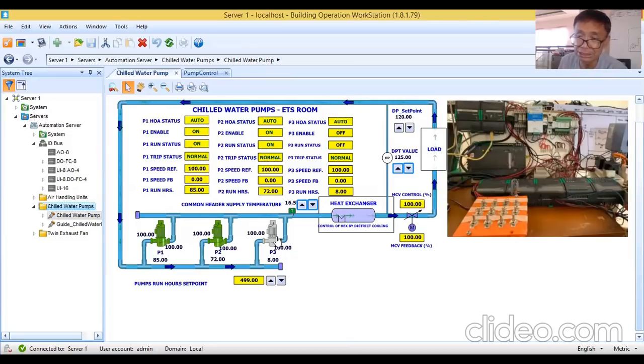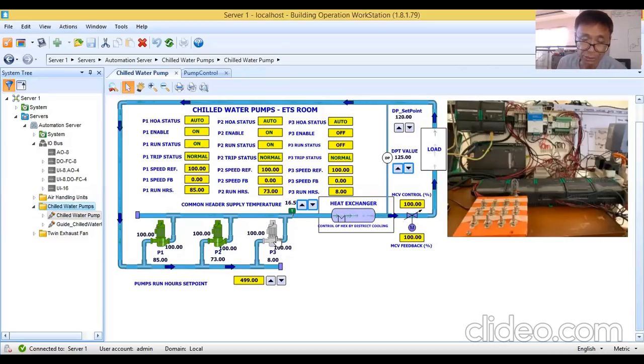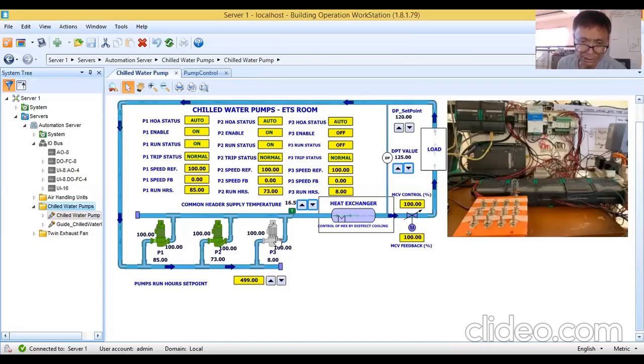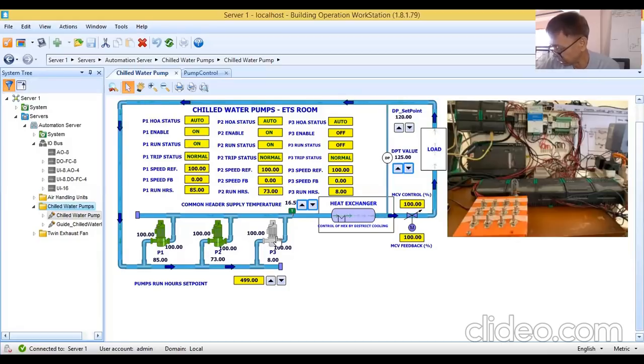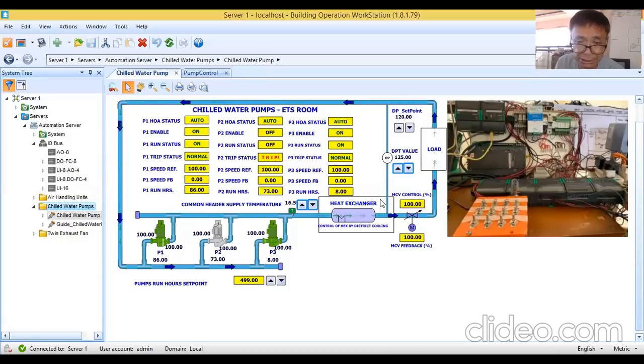Simulating pump one trip using the toggle switch — pump one trips. Pump two continues running. Pump three kicks in based on the sequence of operation: if any duty pump (pump one or pump two) trips, pump three activates. Resetting pump one trip brings pump one back. The control logic isn't fully flexible yet — after a trip, pump three should ideally stay on and then sequence based on runtime. Then testing pump two trip — pump three kicks in again.